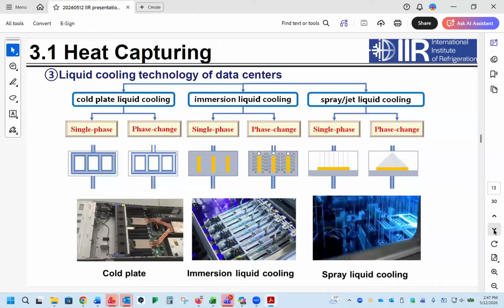One is contact liquid cooling, meaning the coolant connects directly to the electronics side—this includes immersion cooling, spray cooling, or jet liquid cooling systems. Originally, since the current coolant's chemical and electrical performance wasn't very good, before that we used cold plate liquid cooling, where the coolant inside the cold plate is not in direct contact with the electronics. This way we can just focus on increasing thermal performance without worrying as much about chemical and electrical performance.